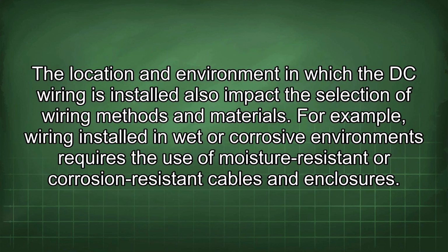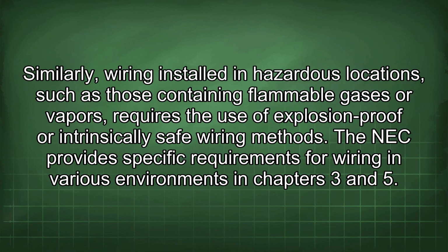The location and environment in which the DC wiring is installed also impact the selection of wiring methods and materials. For example, wiring installed in wet or corrosive environments requires the use of moisture-resistant or corrosion-resistant cables and enclosures. Similarly, wiring installed in hazardous locations, such as those containing flammable gases or vapors, requires the use of explosion-proof or intrinsically safe wiring methods. The NEC provides specific requirements for wiring in various environments in Chapters 3 and 5.